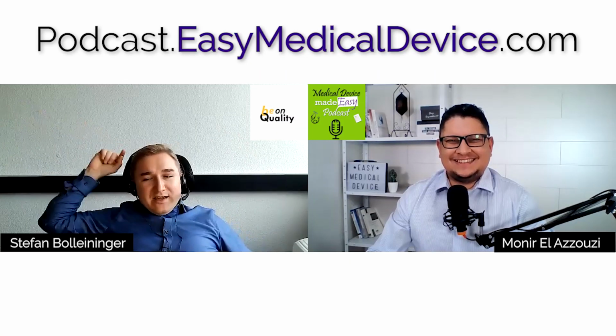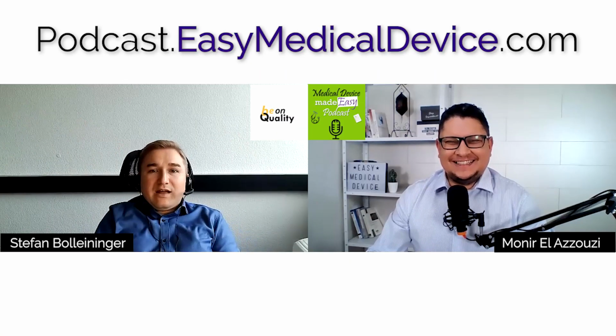But we always need to consider that a device has an essential performance which it shall fulfill. And this one cannot be fulfilled because the manufacturer tells us that it's single use, you don't use it anymore. The other party tells us, yeah, with our cleaning and disinfection, we can use it as a multiple-use, not single-use device. And then the manufacturer tells me, I'm fine with it. It's not my device anymore because you have reprocessed it. It's all your fault. Exactly. And that is the thing.